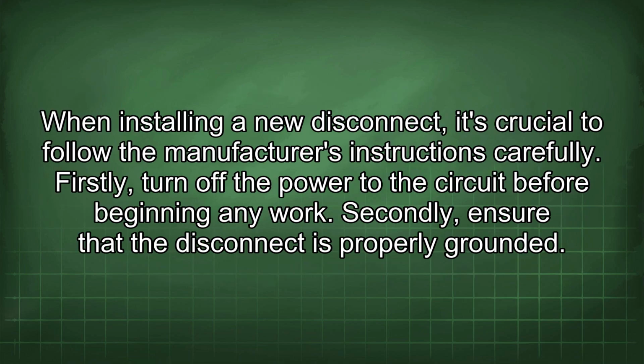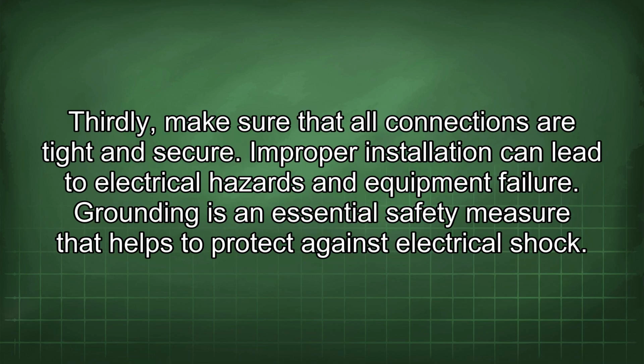When installing a new disconnect, it's crucial to follow the manufacturer's instructions carefully. Firstly, turn off the power to the circuit before beginning any work. Secondly, ensure that the disconnect is properly grounded. Thirdly, make sure that all connections are tight and secure. Improper installation can lead to electrical hazards and equipment failure.